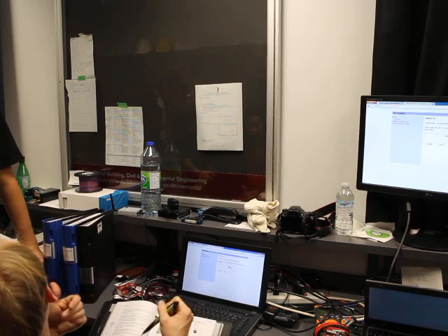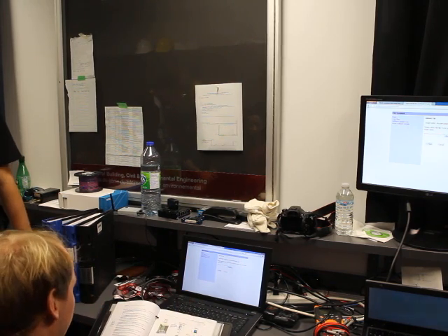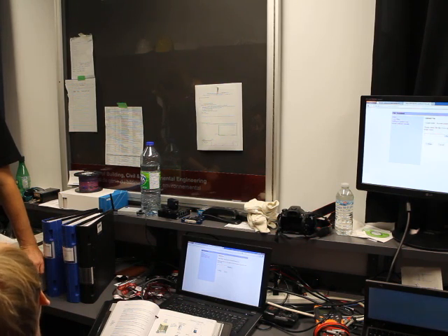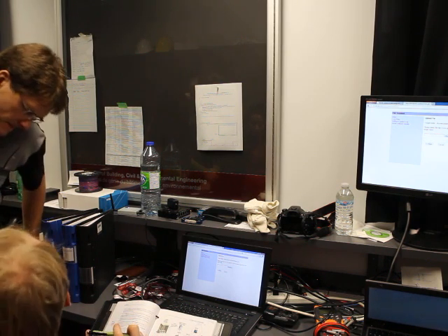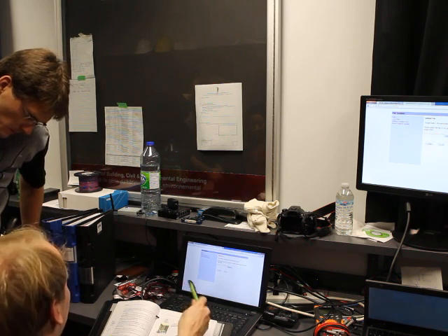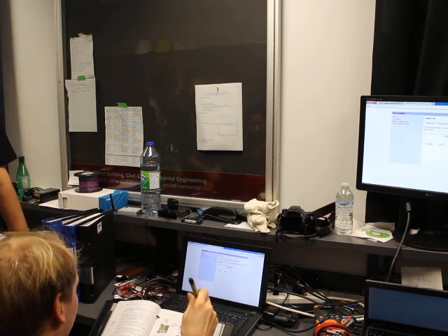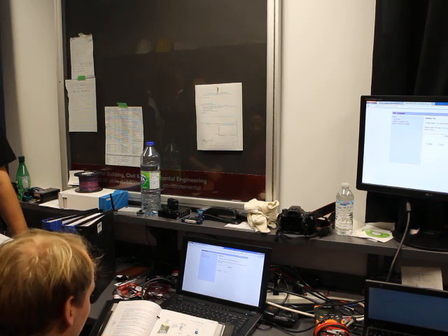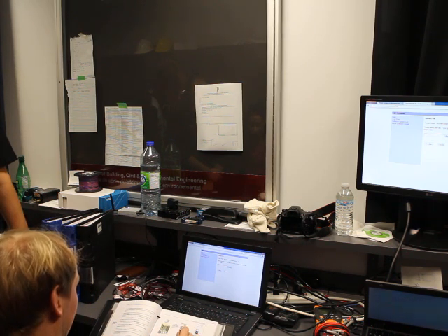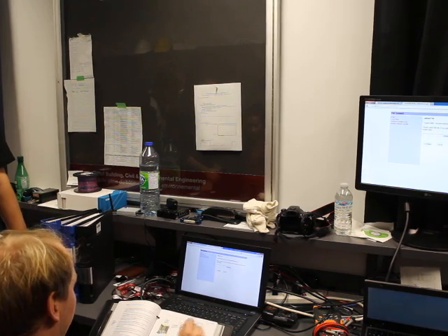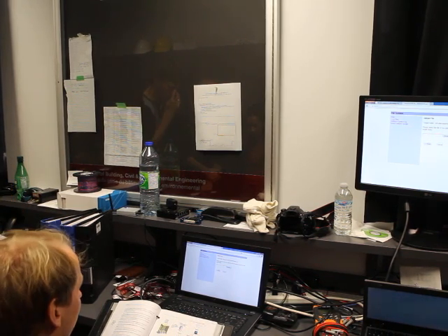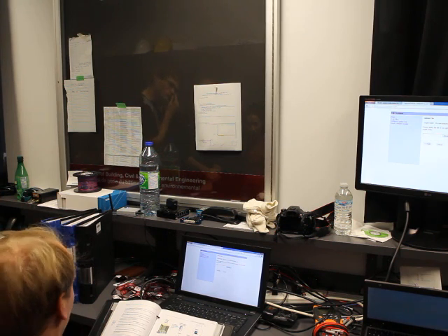CAN is the protocol, like a bus system. But we also have a connection to the collector test platform with Ethernet. There's a data acquisition unit on the collector test platform, and some controllers. So it can also access the mobile lamp field. The Atlas cabinet here is also connected by Ethernet. So that's how the communications network works basically.